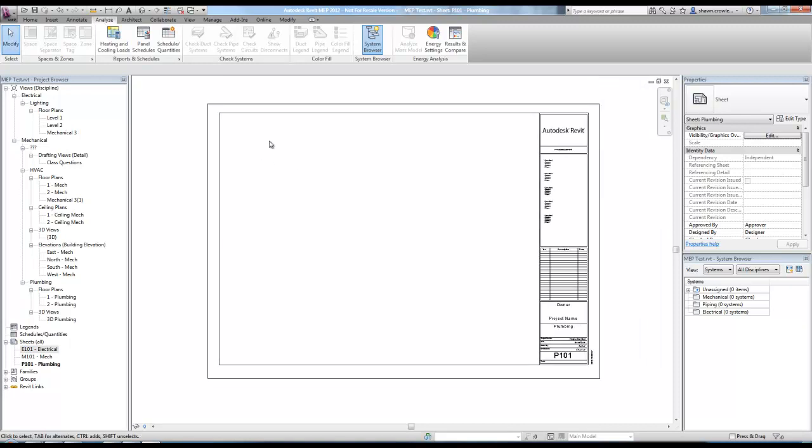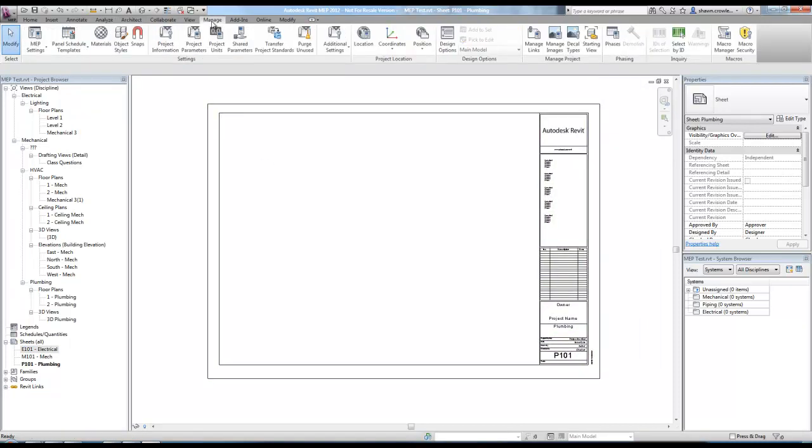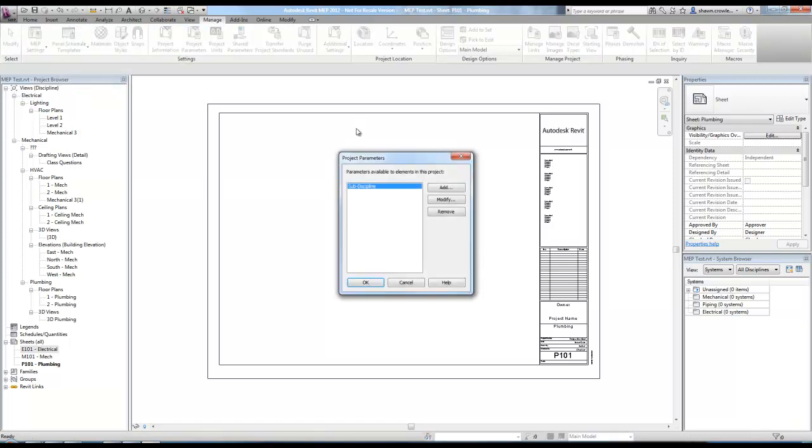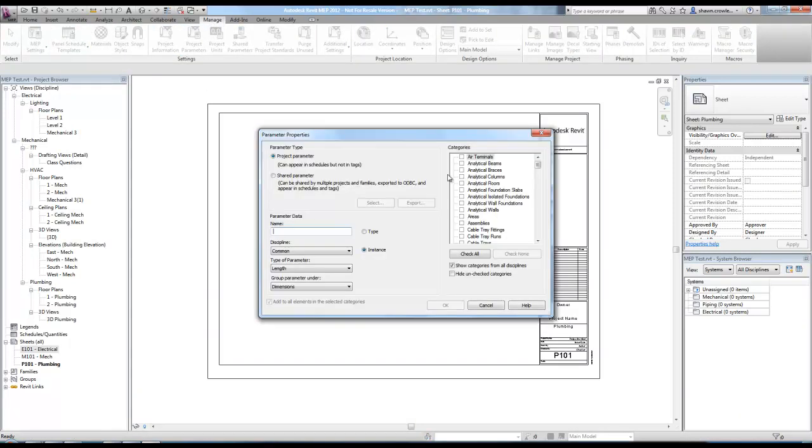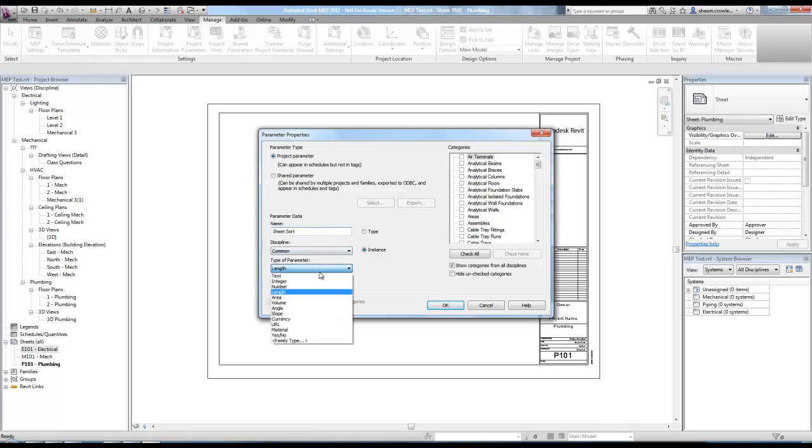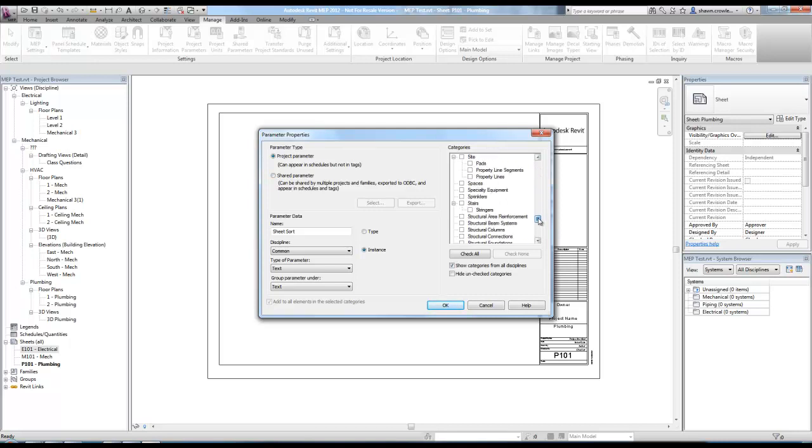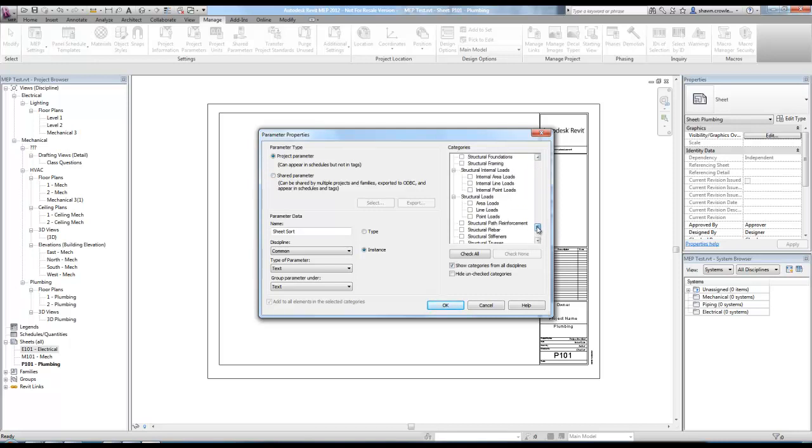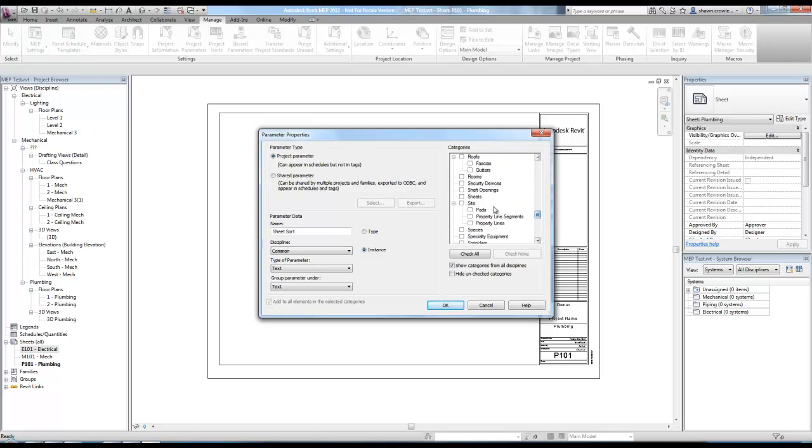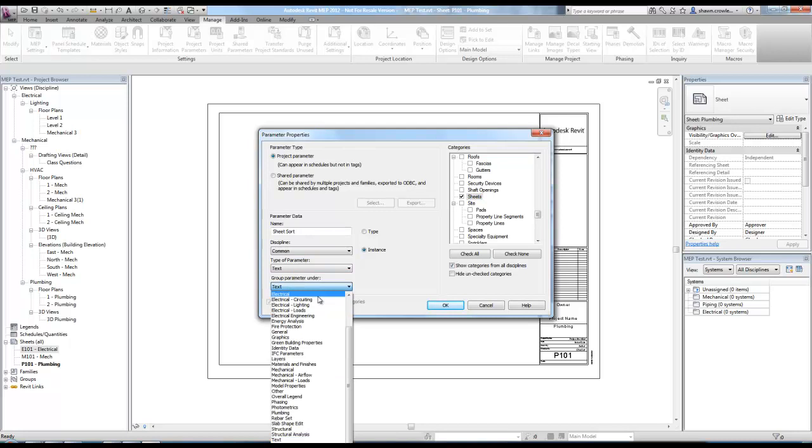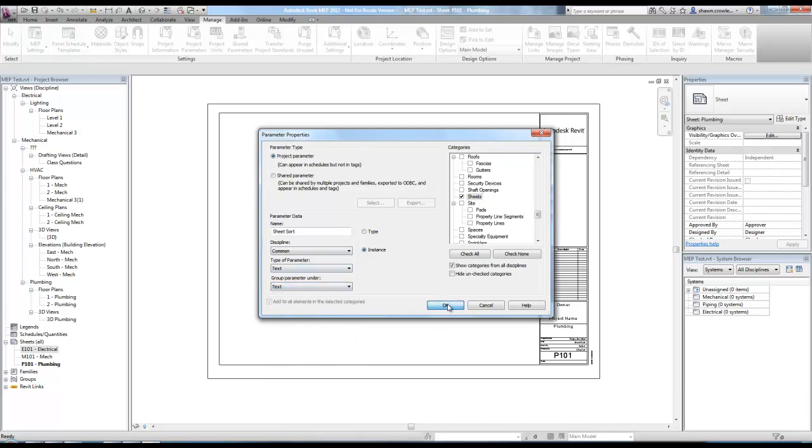You'll notice they're sorting alphabetically, but for the most part it's kind of a standard to have mechanical, electrical, then plumbing. So the question is how can we sort this and keep it clean how we want it. Basically we're going to add a parameter and it's going to be a project parameter. So what I'm going to do is go under the manage tab, project parameters here, and I'm going to add a parameter and it's just going to call it sheet sort.